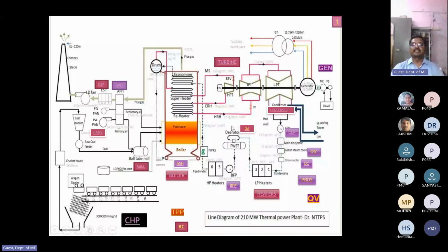One is chemical deaeration, another one is thermal deaeration. In the chemical method, we mix some chemicals, like ammonia, in the tank. Due to chemical reaction, the gases escape from the feed water. Another one is thermal deaeration. Thermal deaeration means increasing the temperature by using steam.